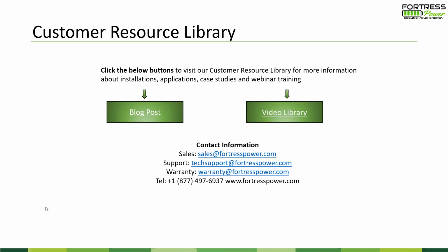What is the recommended breaker size for the Fortress eFlex when using a battery combiner? I actually don't recommend using inline overcurrent protection. You're more than welcome to. The Victron Lynx has a very cost-effective battery combiner system, which coincidentally uses inline fuses. But the battery itself has a fuse for catastrophic events inside the eFlex. The BMS control also regulates over amperage.